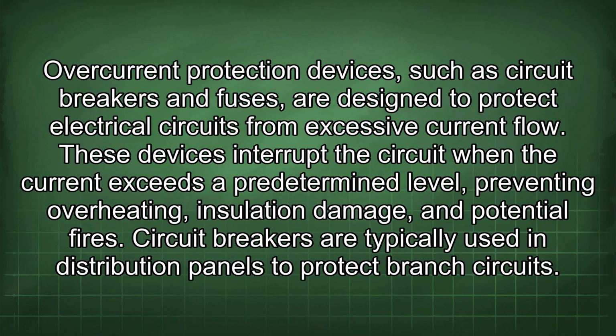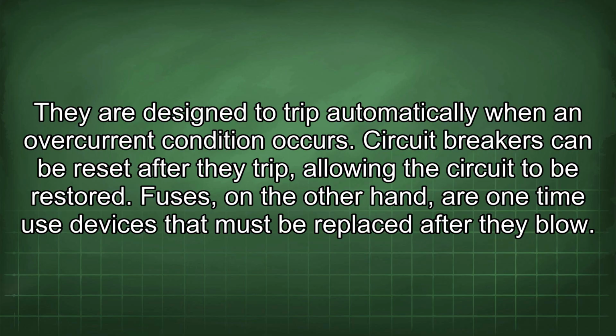Overcurrent protection devices, such as circuit breakers and fuses, are designed to protect electrical circuits from excessive current flow. These devices interrupt the circuit when the current exceeds a predetermined level, preventing overheating, insulation damage, and potential fires. Circuit breakers are typically used in distribution panels to protect branch circuits. They are designed to trip automatically when an overcurrent condition occurs.